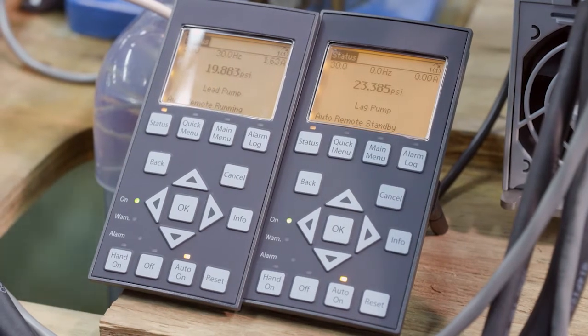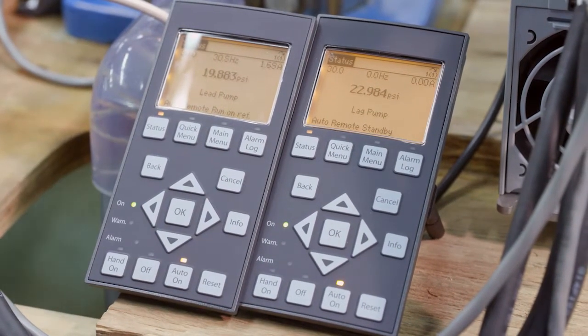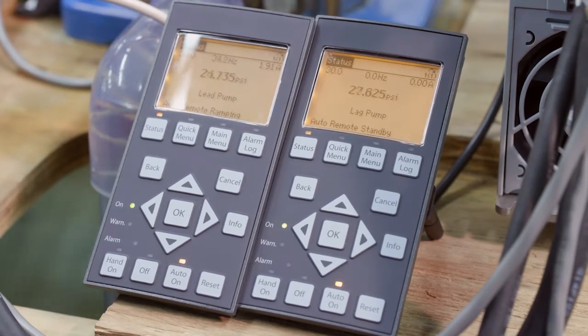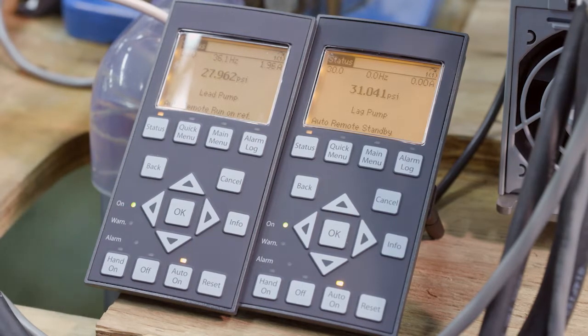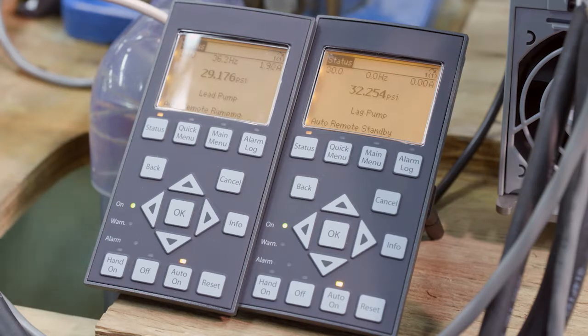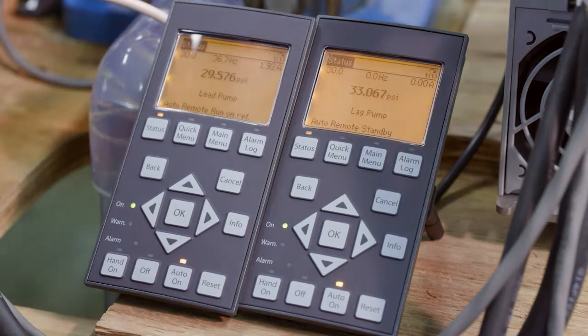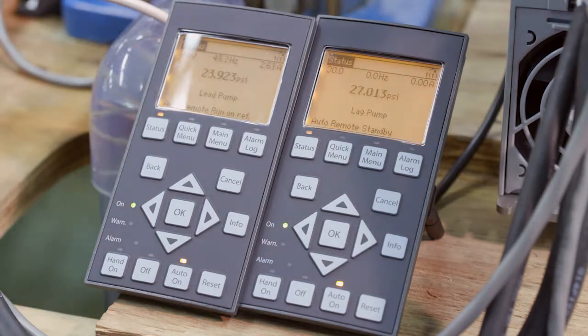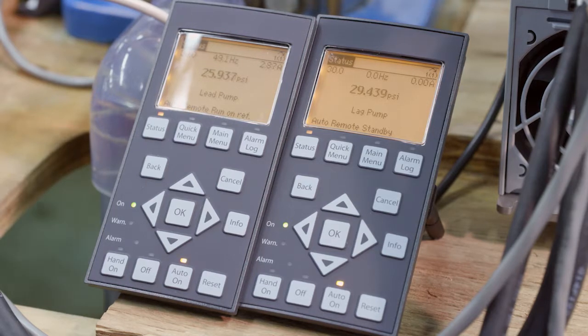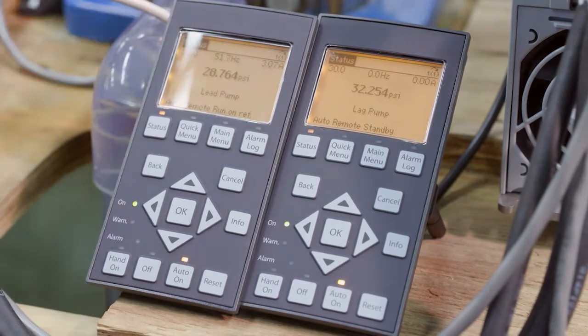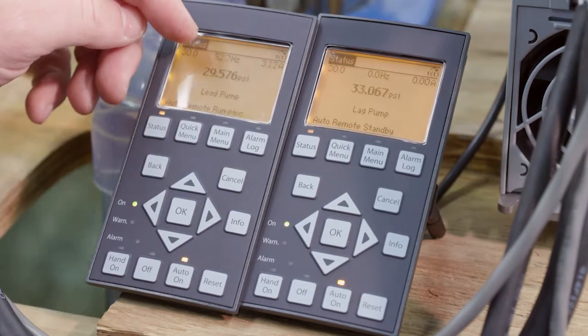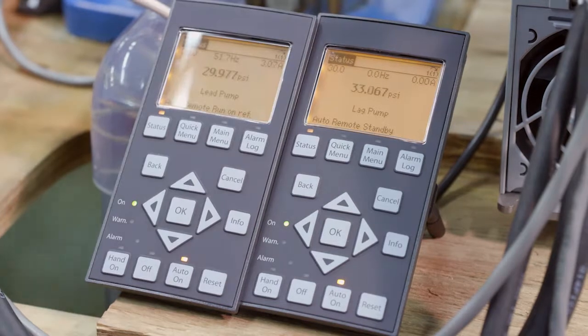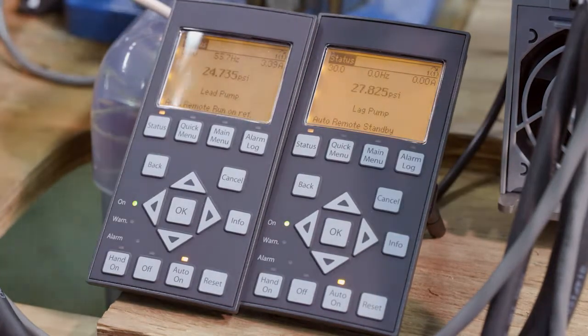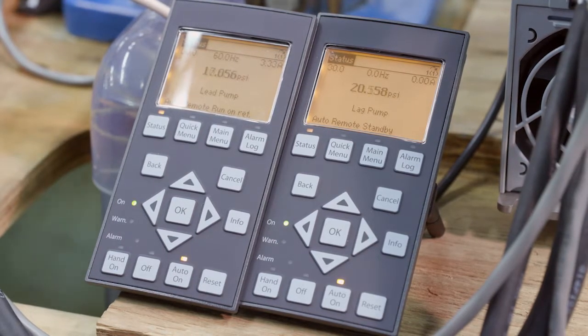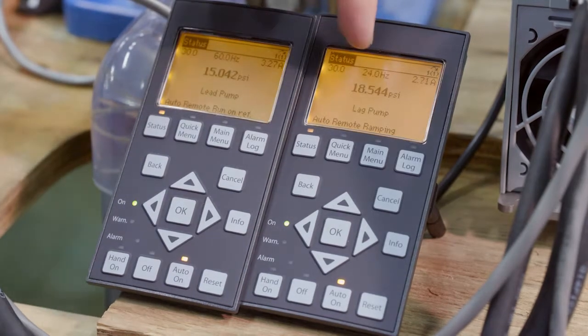So my lead pump is still on, comes on first. Again, we can see the frequency of 35, 36. Able to meet the demand. Set point of 30, so I'm going to open up the valve. So again, now the staging process will begin. Remember, staging was 95%, so 95% of 60 is 57. So when this hits 57, there's going to be a delay, and then pump 2 is going to come on. So it hit my 95%, there's a delay, now my pump 2 comes on.